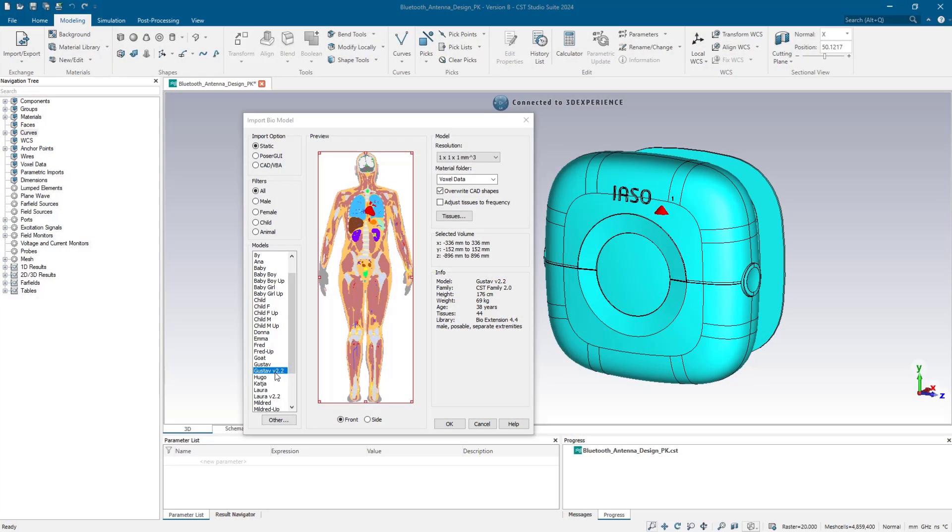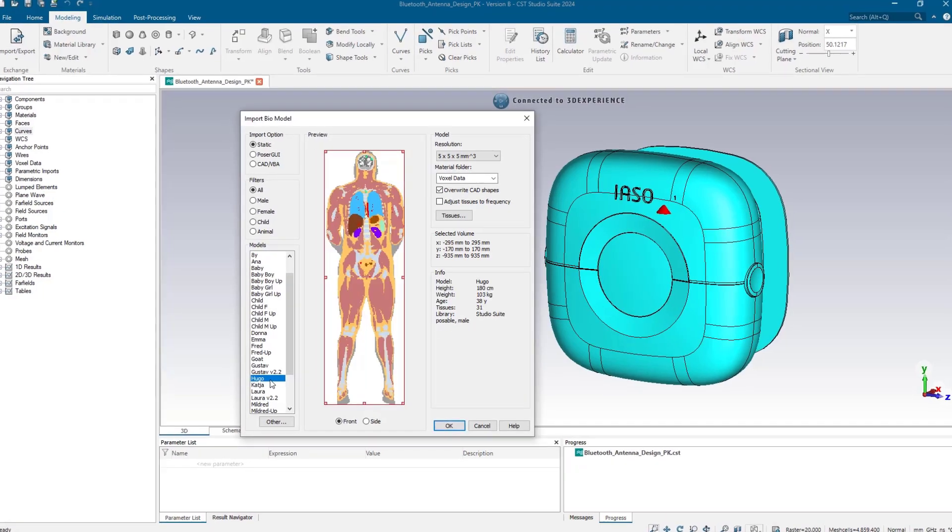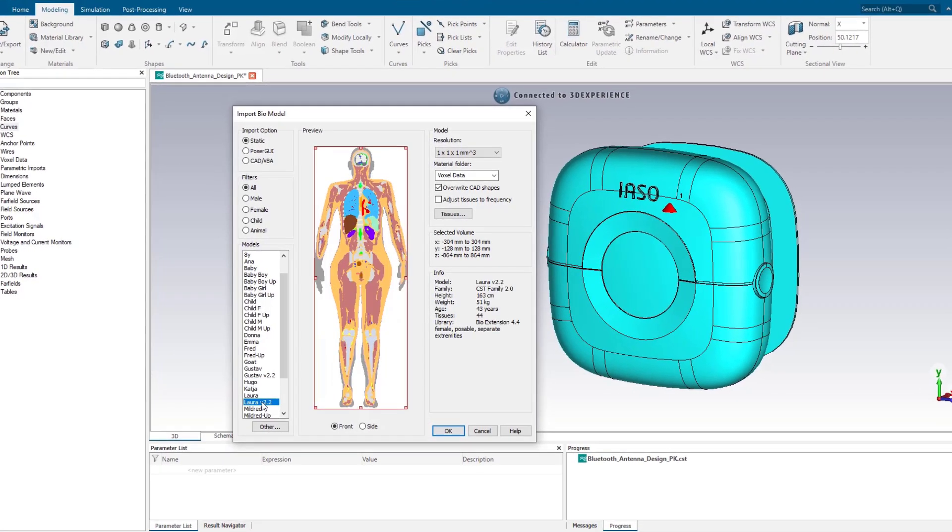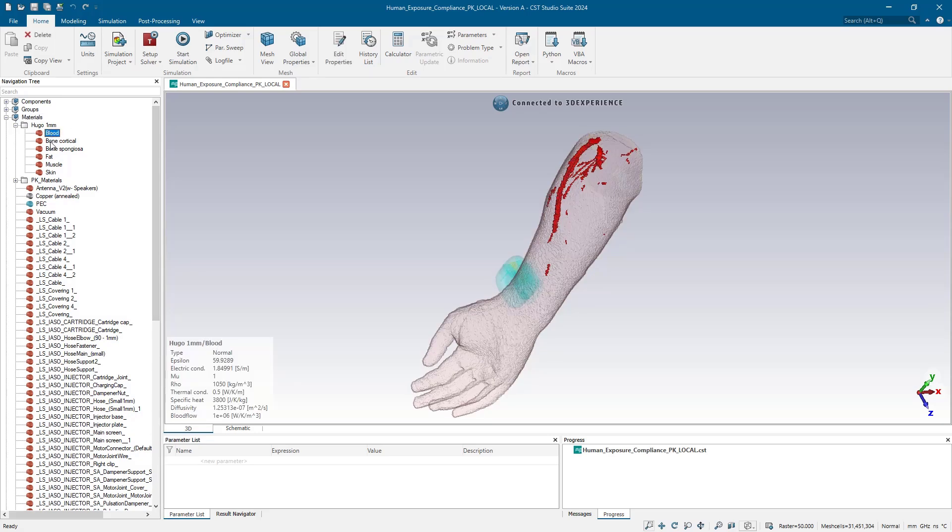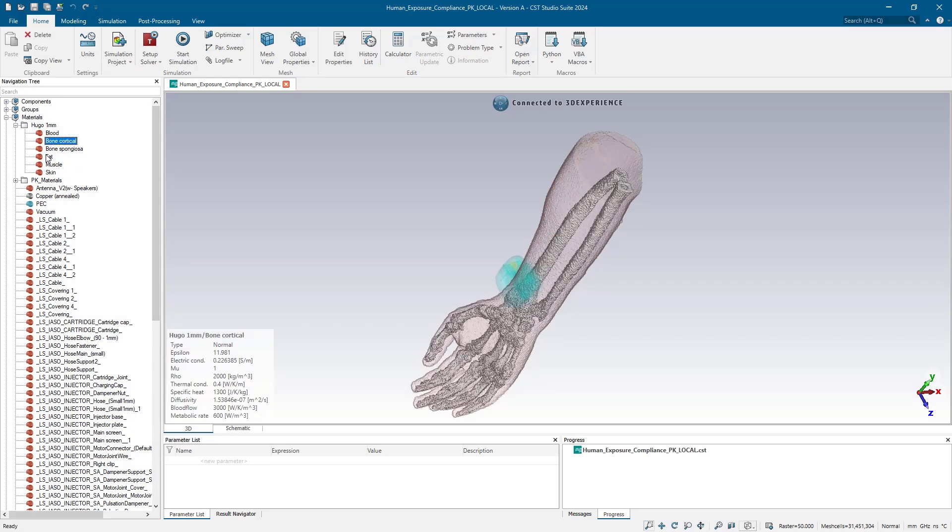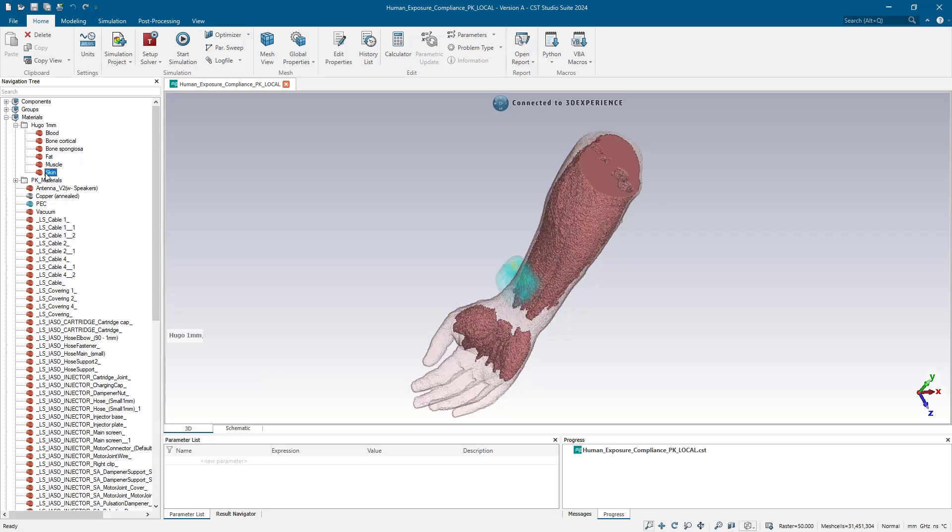For devices like this, the FCC specifies a maximum specific absorption rate. From CST's built-in biomodels library, we can import a human arm and run a specific absorption rate, or SAR, study. These detailed biomodels include skin, blood, bone, muscle, fat, and they're fully posable.